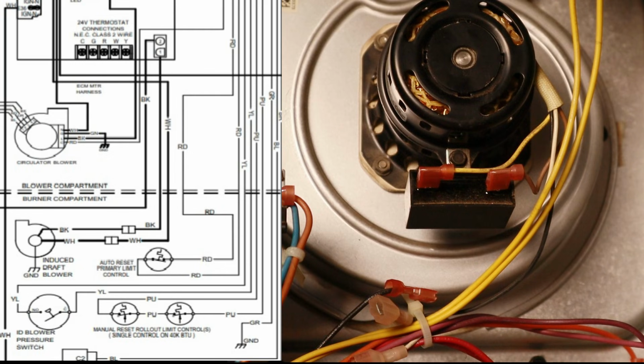So going back to the schematic we're using today, it doesn't tell you that the inducer motor is one of the first things that are going to come on in a furnace when you're calling for heat. So when you get that 24 volt signal coming back from your thermostat on that W terminal on your control board, one of the first things that should happen is your inducer motor should come on. And because it's not coming on, we're going to have to diagnose and figure out what's wrong.